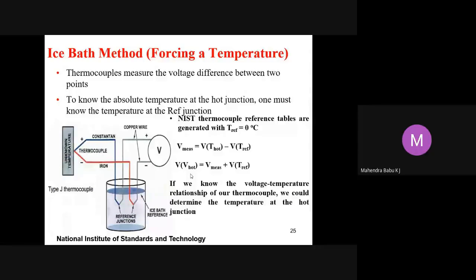NIST, the National Institute of Standards and Technology, thermocouple reference tables are generated with a reference temperature of 0 degrees Celsius. So the measured voltage is equal to the voltage at the hot junction minus the voltage at the reference temperature. Or the voltage at the hot junction is equal to the measured voltage plus the voltage at the reference junction. That means if we know the voltage-temperature relation of our thermocouple, we can determine the temperature at the hot junction. So is it really that easy?